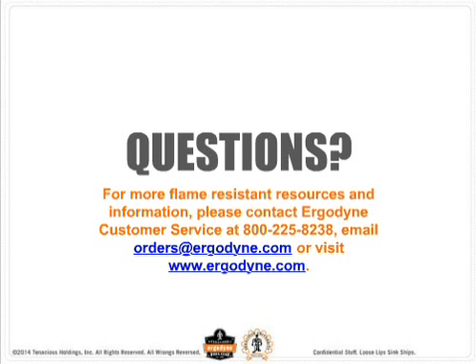No, I would say that's a great question. Actually, you'll see that even in FR arc-rated fabrics, some of them use some synthetic blends. As long as it's a very small percentage of synthetic, added for stretchability or some sort of comfort reason, it doesn't affect the overall performance. In the case you're talking about, a 98% cotton and 2% poly, most likely that fabric blend is not going to melt and drip. It's going to take on the properties of cotton, so you're probably okay there. But with that said, it's probably best to err on the side of caution. I wouldn't push it too much, but I think a 98% cotton, 2% synthetic blend is probably okay. I wouldn't push it any farther than that.